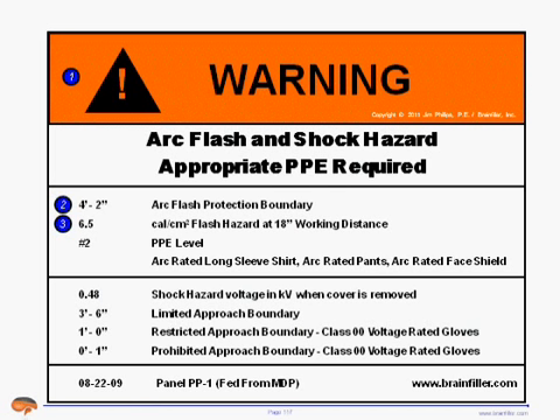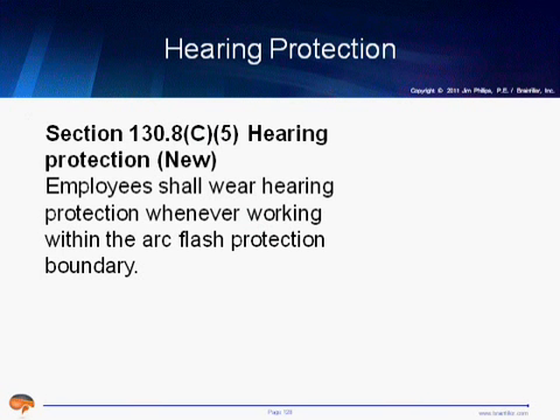Number 3, this would be the calculated incident energy. Some still put the PPE level. You're prohibited from having the HRC, the hazard risk category. Some still use levels, some don't, but you're going to have at least the calculated incident energy or the arc rating. A few will actually list the PPE. More and more people are getting away from that since the list tends to evolve. And then some will also include the shock boundaries, the voltage, the limited approach boundary, restricted approach boundary, prohibited approach boundary. The date is to be a new requirement. And then some will also list what equipment this is being fed from, as well as who performed the study and the computer file for the study.